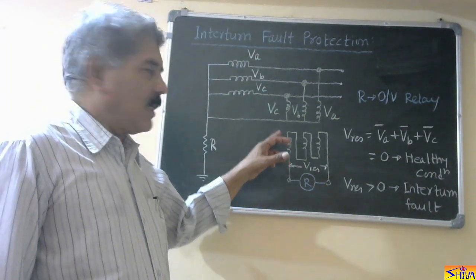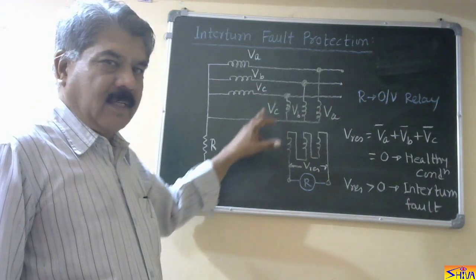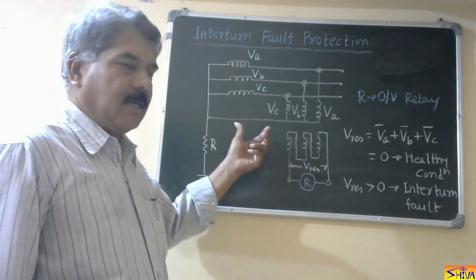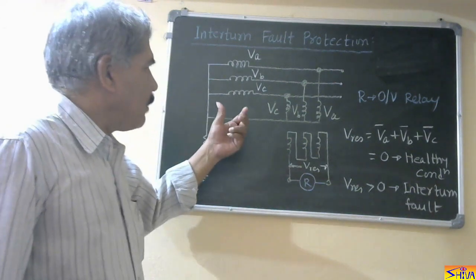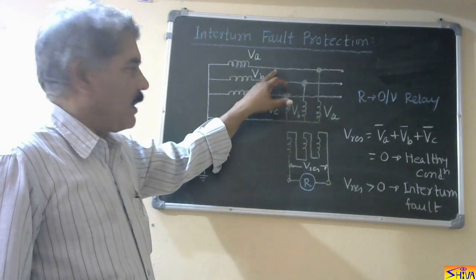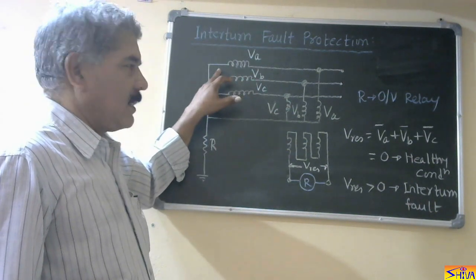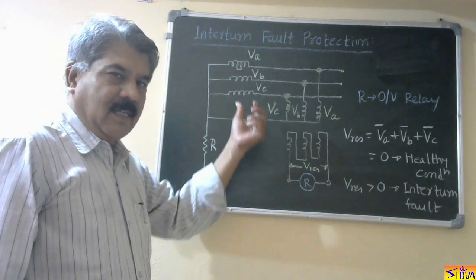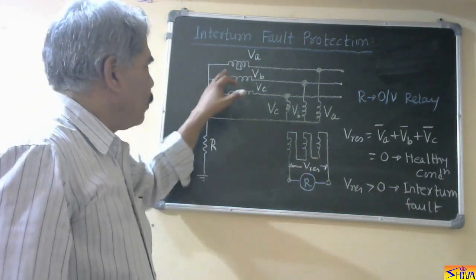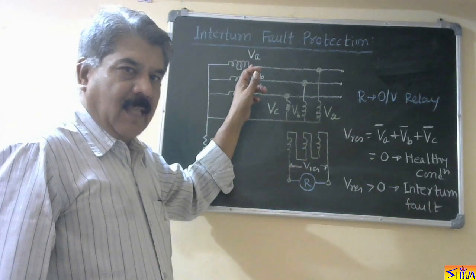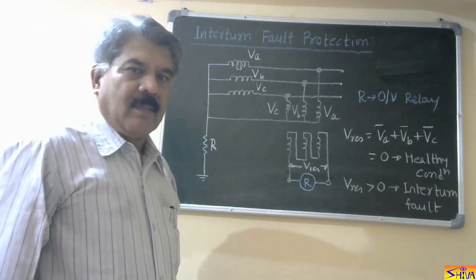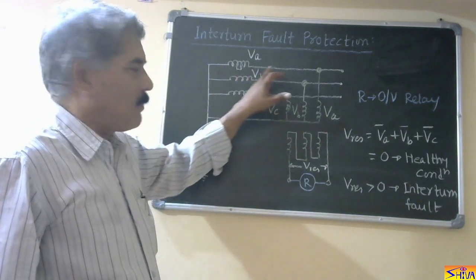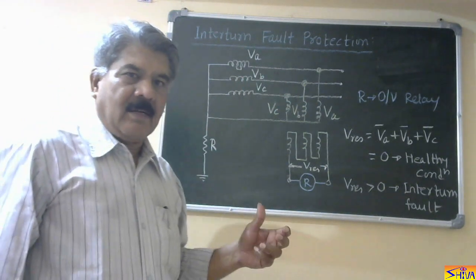When we use a percentage differential relay, one set of CTs is on this side and one set of CTs is on this side. When there is a phase-to-phase fault, the differential current flows and the relay trips. Now, in the case of an inter-turn fault, let us consider the A-phase winding. One CT is here, the second CT is here. Inter-turn fault means a few turns of the same winding — that is the phase-A winding — get short-circuited. So the induced EMF in that particular phase will reduce, and obviously the current will also reduce. But this reduced current will flow through both CTs on each side of the winding, so the differential current will be zero.